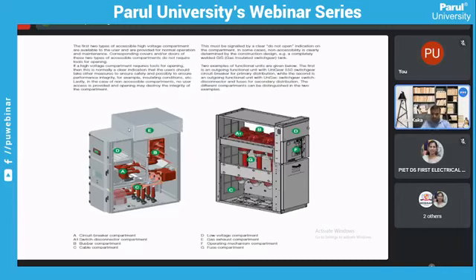the operator can access in case of any fault seen in any of the panels due to an internal arc. All these panels are normally tested for an internal arc classification, and that is somewhere around, let's say my STC value of the breaker is 25K or 31.5K, breakers are normally tested for an internal arc of 31.5 or 25K for 1 second. And that ensures a bit of operator safety because for 1 second, with the insertion of an arc inside a switchgear, at least deformations won't be beyond the IEC acceptable limits. So that ensures the protection of an operator standing in front of the switchgear. As we know, the protections will be triggering quite a bit faster than 1 second. So that's the purpose of testing an IEC internal arc test for 1 second in switchgears.